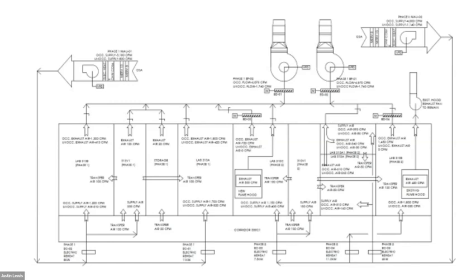This project includes 2 laboratory suites at a college. The labs work with insects, so pressure cascades were absolutely critical. We needed to make sure that insects couldn't escape. They had a very, very tight tolerance that needed to be adhered to. But one interesting thing we found when we started reviewing the documents was we had an occupied mode of operation and we had an unoccupied mode of operation.